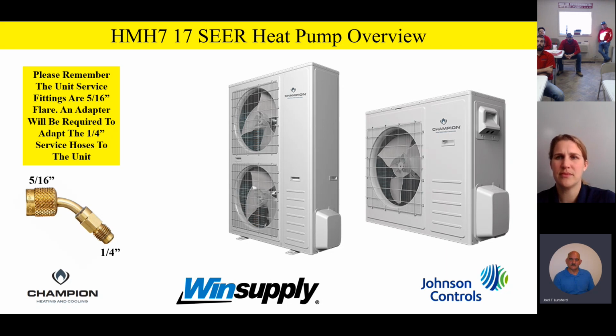And you guys have seen these. Robinair and Yellow Jacket and different companies make them. But they're the same kind of fitting that you'll see like on mini splits. And I want to stress this to everybody. These units are not mini splits. They're not a mini split product. However, they kind of look like a mini split product, but you're going to wire them up and you're going to take suction line out to it and liquid line out to it, insulate your suction line. You're going to treat it just like a regular old heat pump.